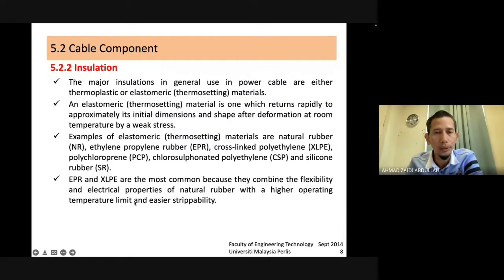Okay. And then the EPR and XLPE are the most common, as I mentioned lah kan, because they combine the flexibility and electrical properties of natural rubber with higher operating temperature. Okay, so nanti jangan terkejut, normally when you are dealing with underground cable for TNB, confirm they will ask for XLPE type cable. Okay, JKR maybe they still accept SWA, single wire armoured. Okay, that one is still under thermosetting.